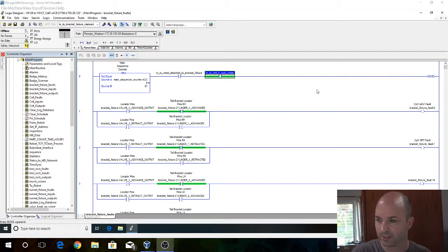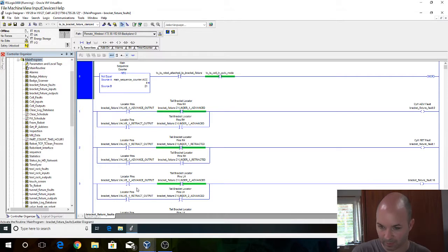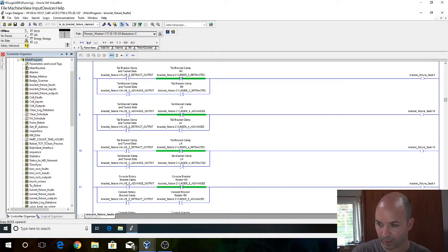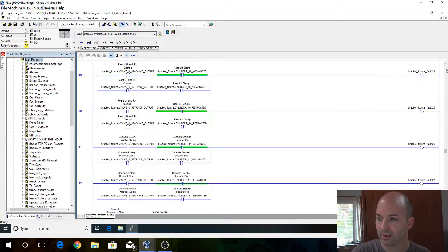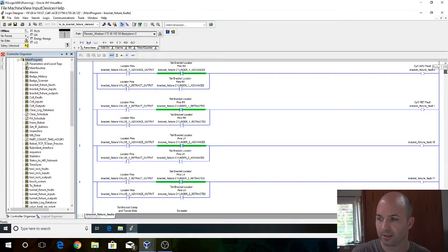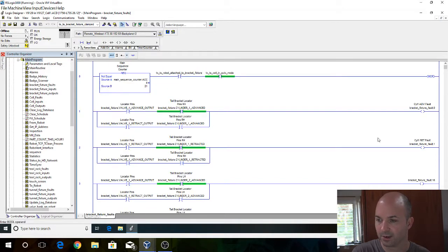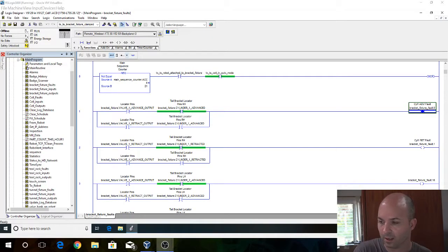The way it works is anything within this MCR range from the top and down all the way to the rung number, it's probably 18, I think is what I checked it at, 27. So you got a second MCR here. It'll only cut on any of these outputs inside of this area. For example, this cylinder 1 advanced fault, that is basically only going to come on when you have a fault on the MCR, and basically all the criteria for the MCR are met.